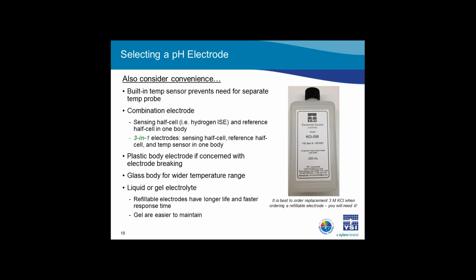All pH measurements need to be compensated for temperature. So rather than having a separate temperature sensor, it is most convenient to have a temperature sensor built into the electrode. An electrode with a temperature sensor, reference half cell, and sensing half cell all in one electrode body is sometimes termed a 3-in-1 electrode. A large number of YSI lab electrodes feature a built-in temperature sensor.